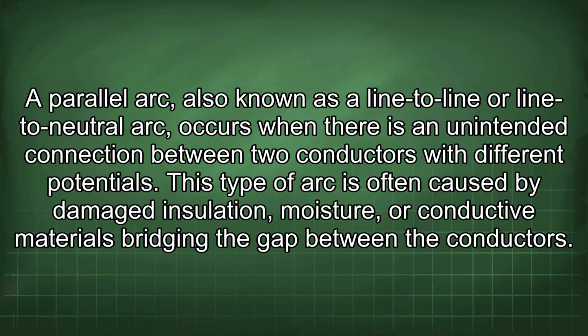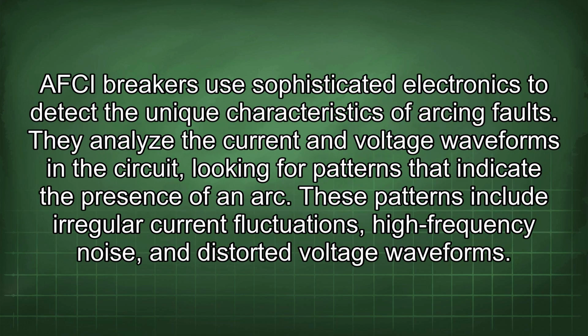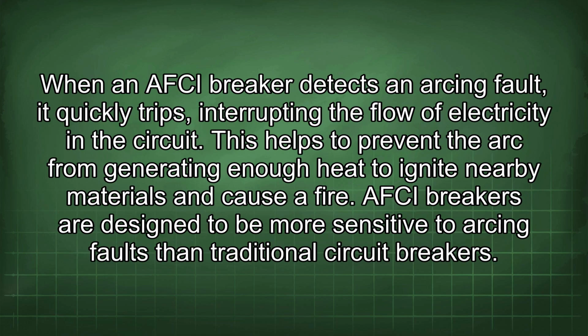A parallel arc, also known as a line-to-line or line-to-neutral arc, occurs when there is an unintended connection between two conductors with different potentials. This type of arc is often caused by damaged insulation, moisture, or conductive materials bridging the gap between the conductors. AFCI breakers use sophisticated electronics to detect the unique characteristics of arcing faults. They analyze the current and voltage waveforms in the circuit, looking for patterns that indicate the presence of an arc. These patterns include irregular current fluctuations, high-frequency noise, and distorted voltage waveforms. When an AFCI breaker detects an arcing fault, it quickly trips, interrupting the flow of electricity in the circuit. This helps to prevent the arc from generating enough heat to ignite nearby materials and cause a fire.